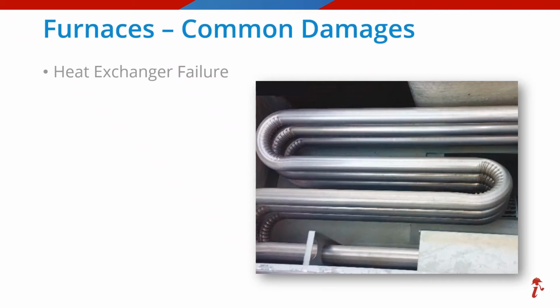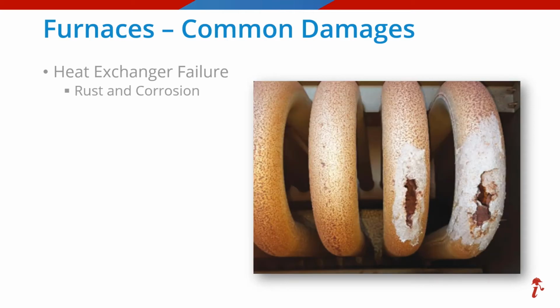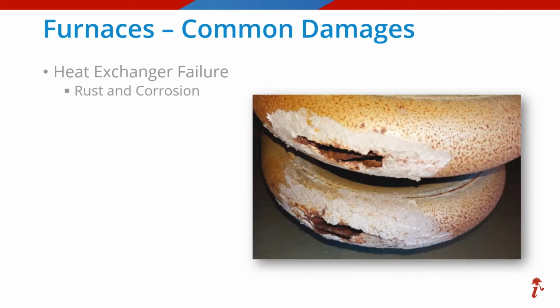Remember those heat exchangers we just talked about during the last few slides? Here is another type, and this is what they should look like if they are in good shape, but that is certainly not always the case. As it turns out, the most common damages to heat exchangers are wear and tear related. And leading the list is rust and corrosion, which is generally caused by age and a lack of maintenance. This is a closer look at that severe rusting on this heat exchanger, and of course this happened over a period of time and was not sudden or accidental.